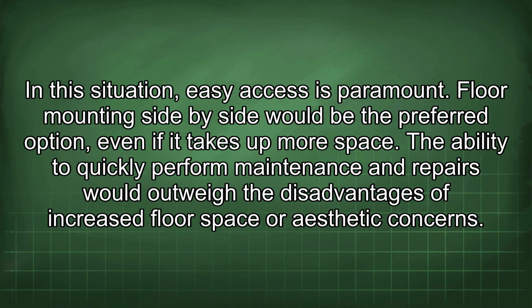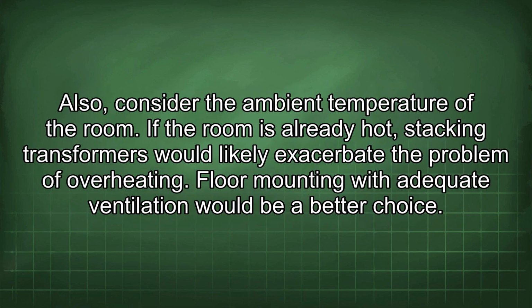In this situation, easy access is paramount. Floor mounting side by side would be the preferred option, even if it takes up more space. The ability to quickly perform maintenance and repairs would outweigh the disadvantages of increased floor space or aesthetic concerns. Also, consider the ambient temperature of the room. If the room is already hot, stacking transformers would likely exacerbate the problem of overheating. Floor mounting with adequate ventilation would be a better choice.